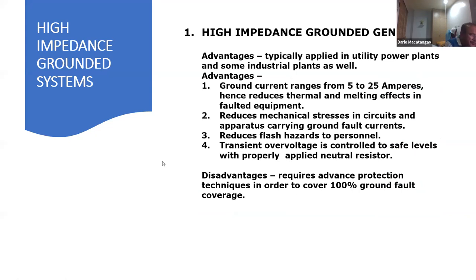One thing to understand in neutral grounding protection is that typically manufacturers will design the generator's short circuit ability up to the three-phase fault only. You design the generator and specify the three-phase fault capability, and then it's there. But the problem is, usually, because of the small zero sequence impedance of generators, the ground fault current tends to be higher than the three-phase fault current.